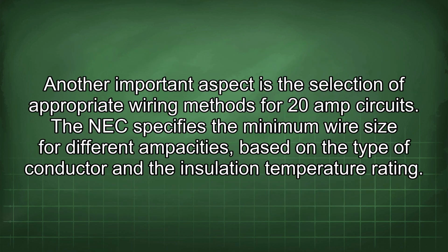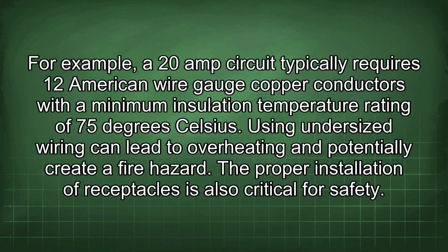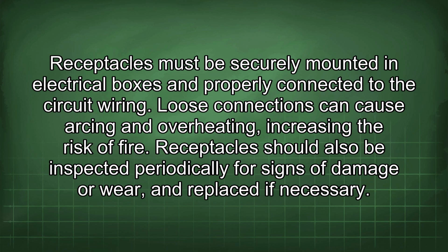Another important aspect is the selection of appropriate wiring methods for 20-amp circuits. The NEC specifies the minimum wire size for different ampacities based on the type of conductor and the insulation temperature rating. For example, a 20-amp circuit typically requires 12 American wire gauge copper conductors with a minimum insulation temperature rating of 75 degrees Celsius. Using undersized wiring can lead to overheating and potentially create a fire hazard. The proper installation of receptacles is also critical for safety. Receptacles must be securely mounted in electrical boxes and properly connected to the circuit wiring. Loose connections can cause arcing and overheating, increasing the risk of fire. Receptacles should also be inspected periodically for signs of damage or wear, and replaced if necessary.